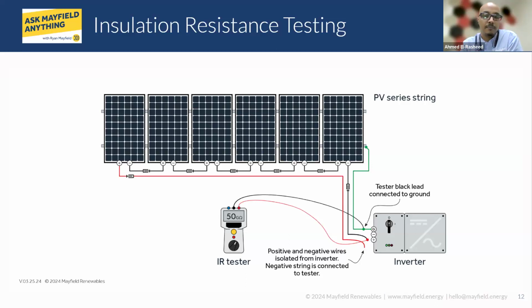And the conventional way of interpreting it, instead of looking at the actual current measurement, is to take a look at the resistance value. If that resistance value is low, you have a leak in that insulation, you have a break to ground. And if it's high, then it's holding the pressure well, and you don't have a fault to ground.